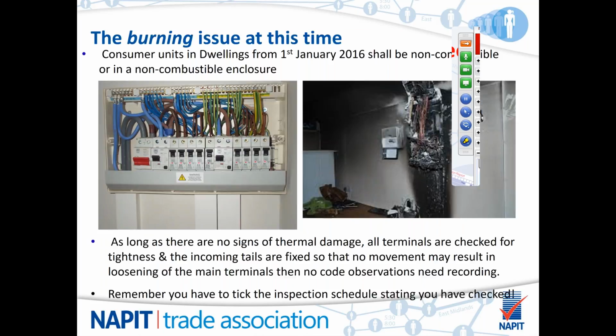Now then, the burning issue. Remember why we had the Third Amendment. It was there to make consumer units non-combustible. And why was this? It's because should there be a problem inside of that consumer unit, it was hopefully that it didn't add fuel to the fire. It was the enclosure that was catching fire, which was the fuel for the fire. So if we took that fuel away by making it metal, then it got rid of that problem.